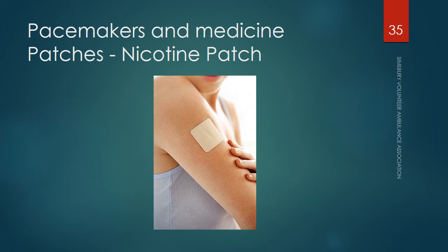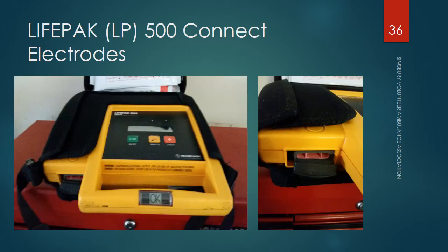A lot of patches have names on them, but the big patches that we're looking at are the ones on the chest, the nitro patches, and staying away from implantable pacemakers or defibrillators, making sure we don't place the pads over those devices. So here we have a picture of our LifePak 500, and you can see the green on-off button, the analyze button, and the defibrillate button. I also highlighted where the electrode fits in. Obviously you've got the handle. This defibrillator reads OK, which means it's in fine working order, has plenty of energy, and doesn't need any type of maintenance. Provided you see the OK sign, all is good.